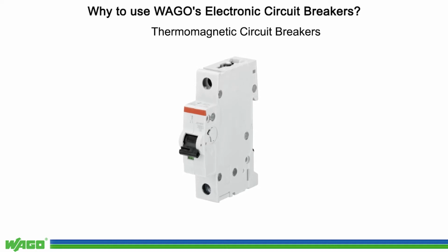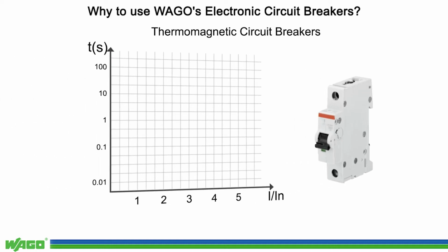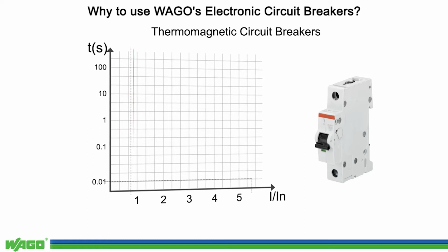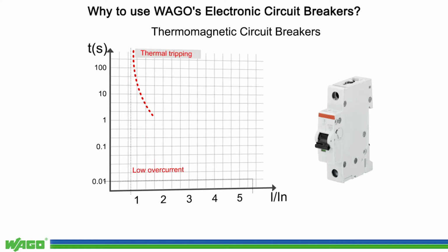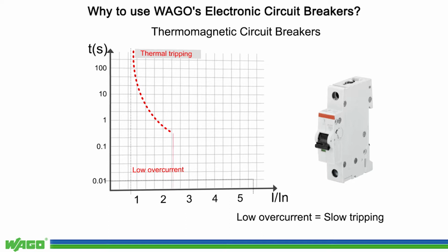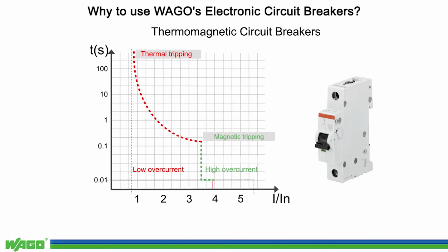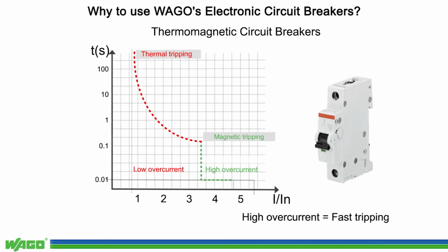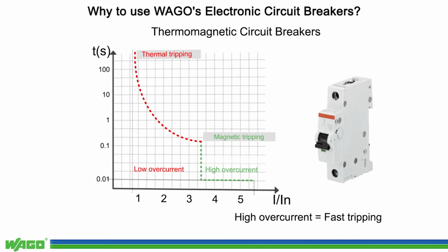Let's have a look at the trip characteristics of thermomagnetic circuit breakers. Their trip behavior depends on the overload. Thermotripping is time-delayed on low overloads. On large overloads, however, magnetic tripping interrupts the circuit very quickly.